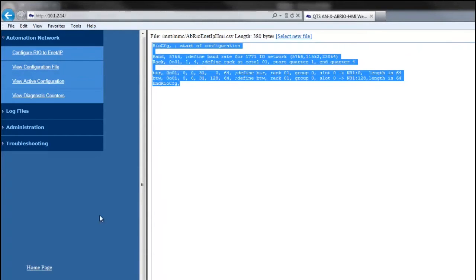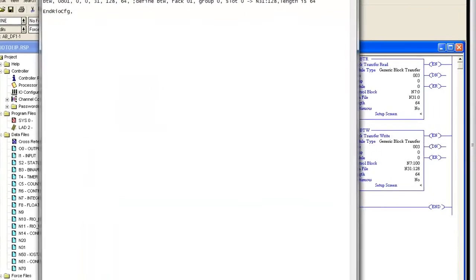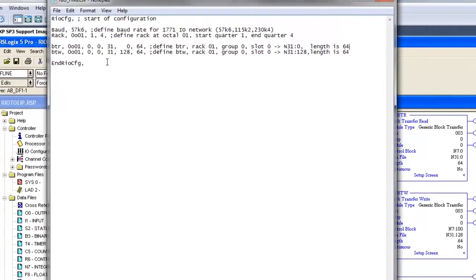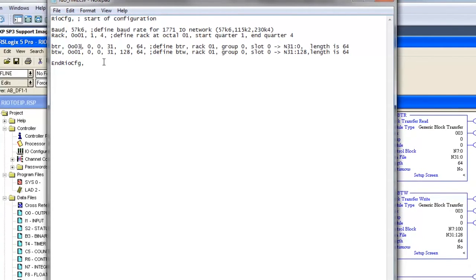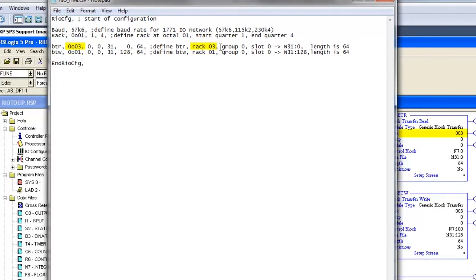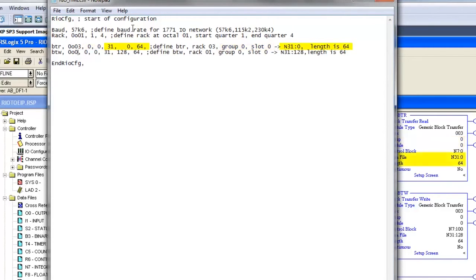So now we need to see the existing BTR and BTW, that's Block Transfer Write and Read values, going to the original HMI and mimic it in the CSV file. The BTR is Rack 3, Group 0, Slot 0, reading into N31-0 for a length of 64.